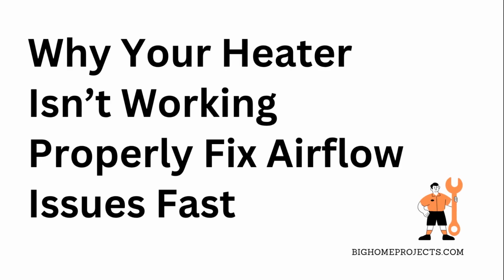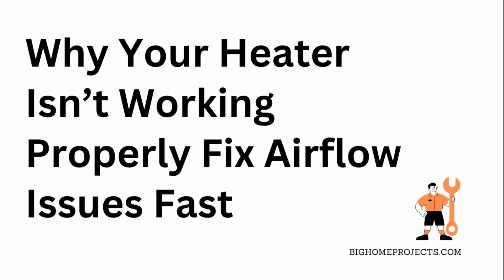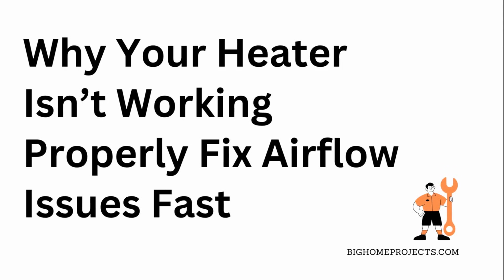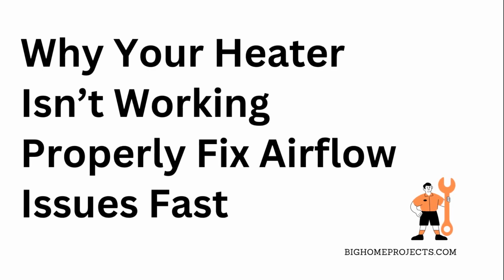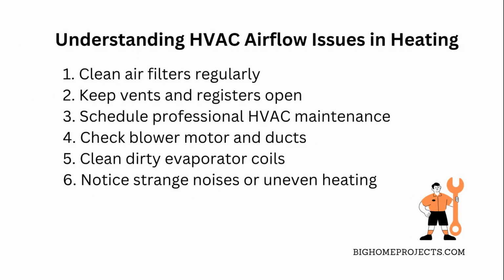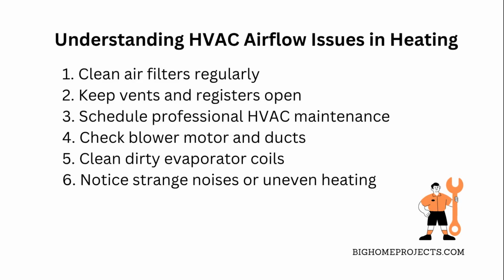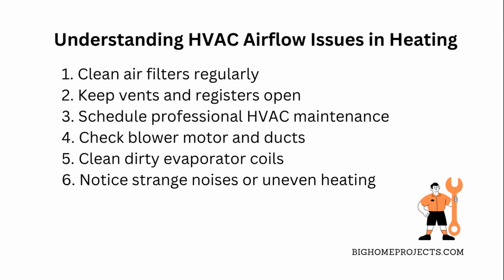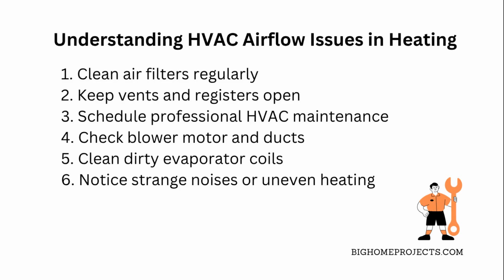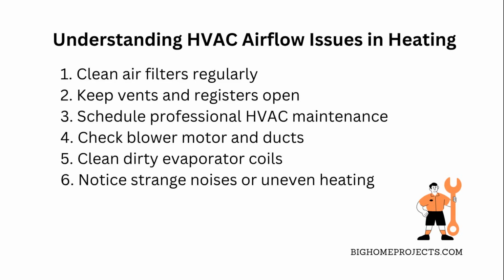If your HVAC system's airflow during heating isn't enough, it can seriously mess with your comfort and safety without you even realizing it. Okay, so when the air isn't flowing right, your heater's working harder than it should, and that can cause some real issues. First off, not enough airflow means the heat exchanger gets way hotter than it's supposed to, which can trigger the high limit switch to shut things down to keep you safe.